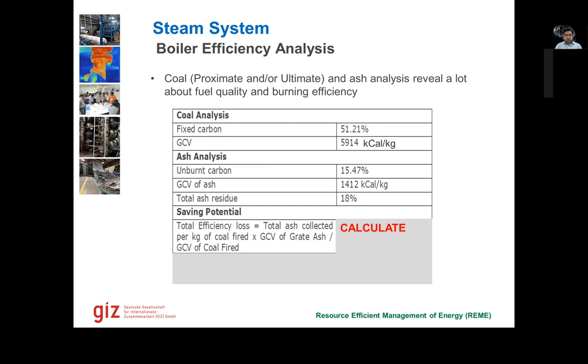Then what we do for solid fuels is that we also do an efficiency analysis of unburnt carbon in the ash. So for the coal, we did the coal analysis. Its GCV was 5914 with fixed carbon of 51.21%. The ash that came out had an unburnt carbon of 15.47% and GCV of 1412 kilocalorie per kilogram. The total ash residue was 18%. And if we use this formula, total ash collected per kilogram of coal fired multiplied by GCV of the ash, divided by GCV of coal fired, then we can calculate the total efficiency loss.